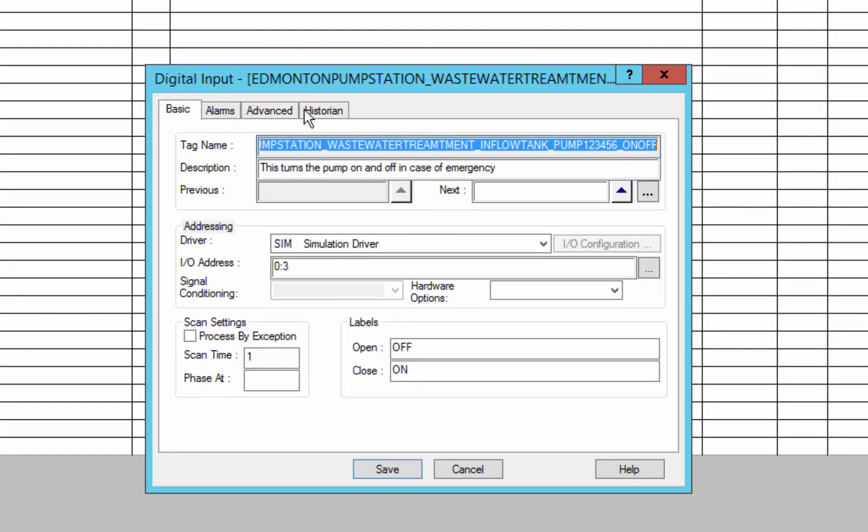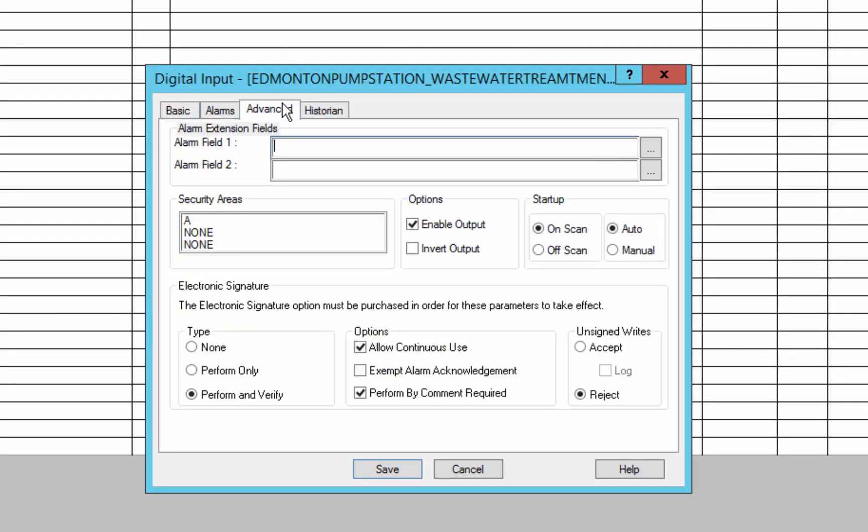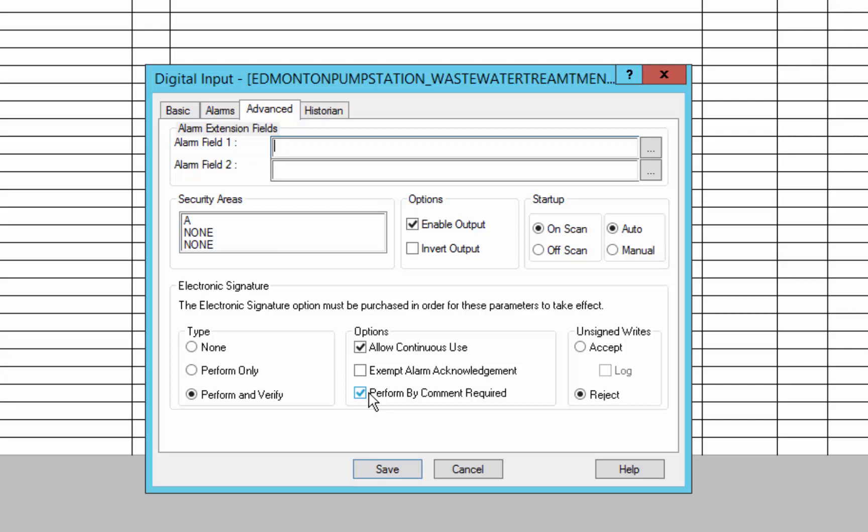So here you can see on a tag in my database, there's a whole section here where I can specify whether to have a perform action or perform and verify action. When a user changes this point, I can allow it to remember the username, I can say whether or not to require electronic signature when acknowledging alarms that happen on this point, and require a comment or not.